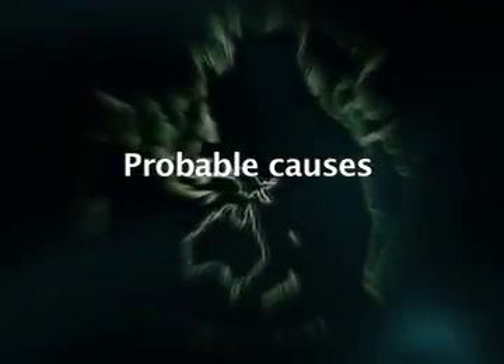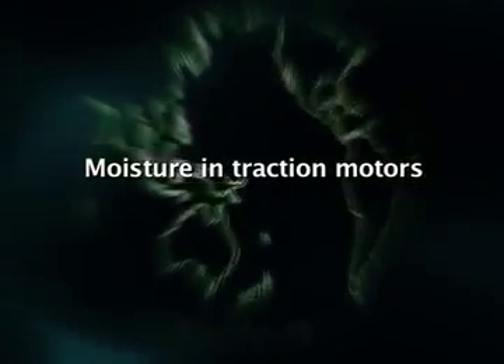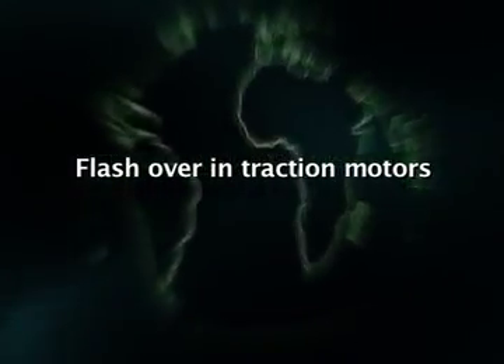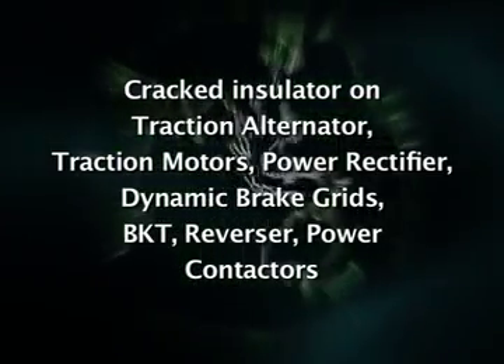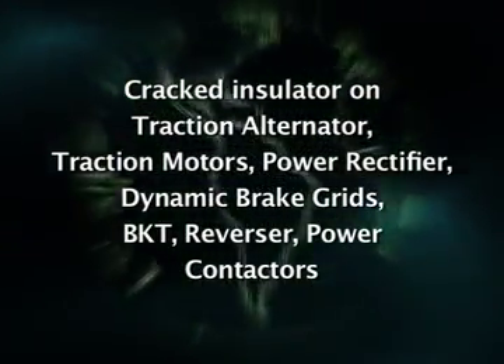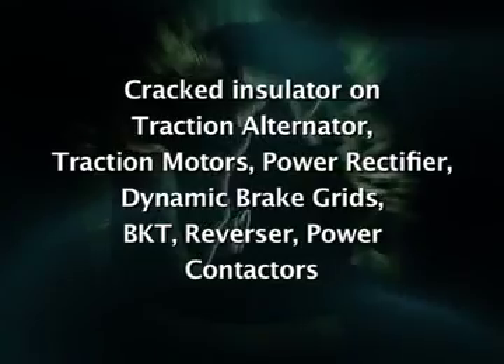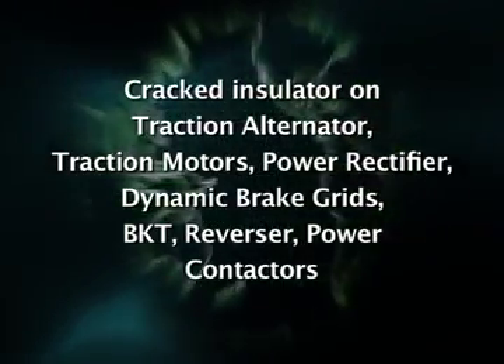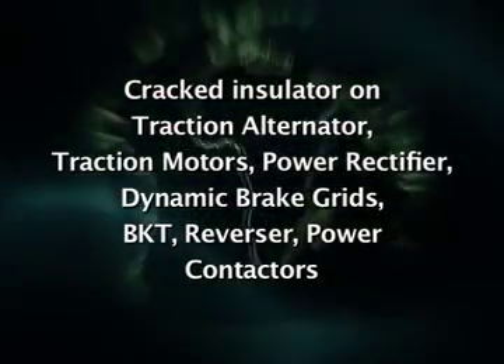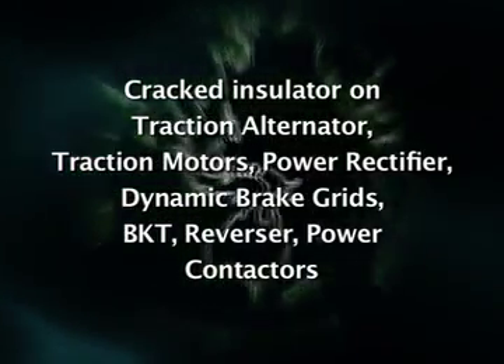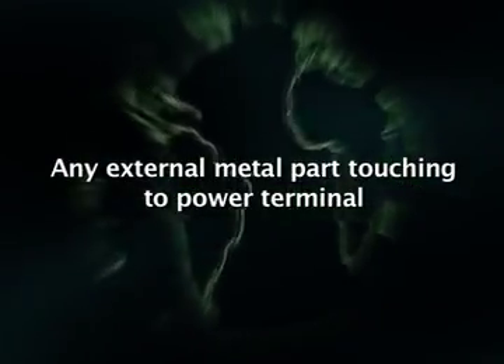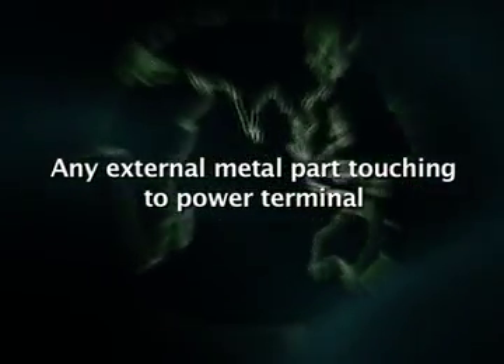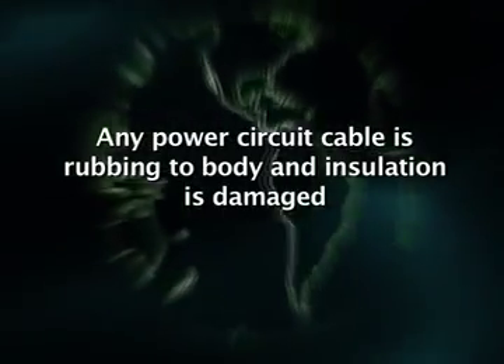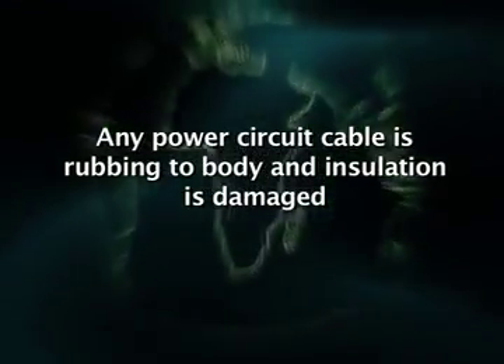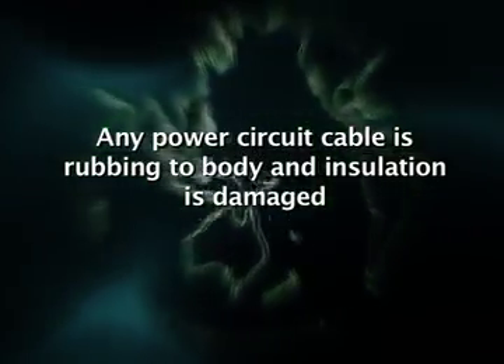Probable causes: moisture in traction motors, flash over in traction motors, cracked insulator on traction alternator, traction motor power rectifier, dynamic brake grids, BKT, REV, power contactor. Any external metal parts touching to power terminal. Any power circuit cable is rubbing to body and insulation is damaged.